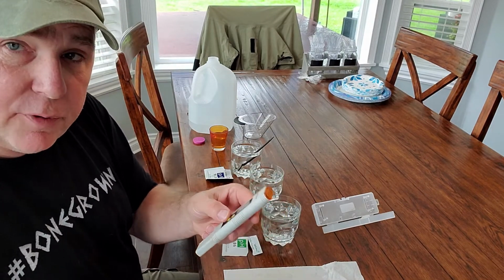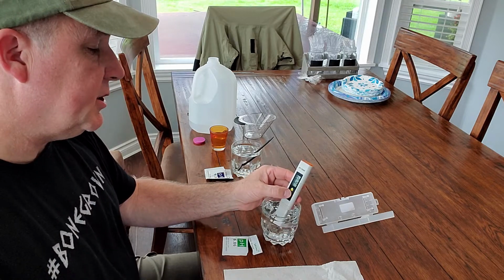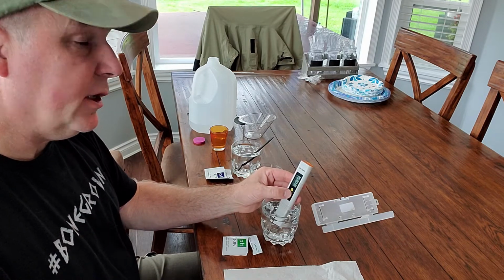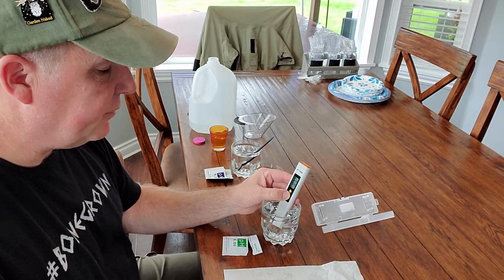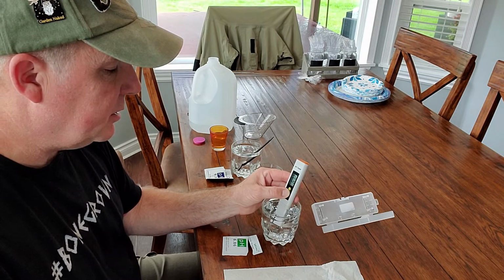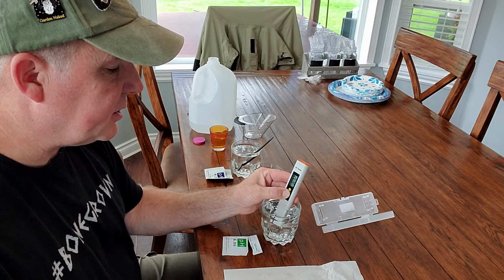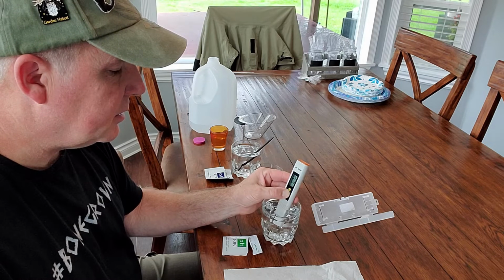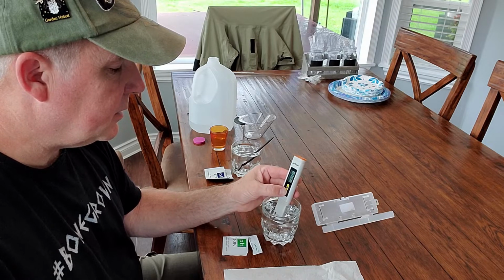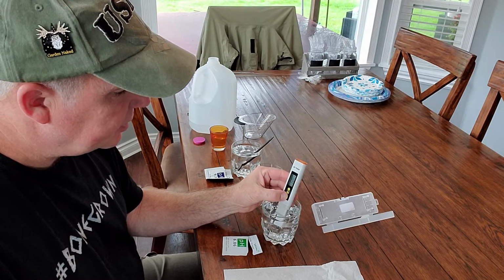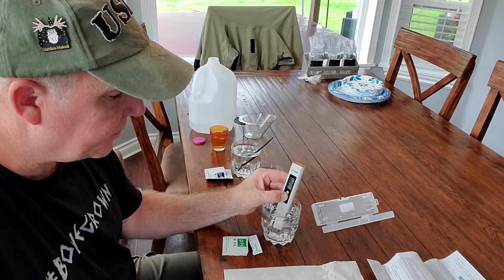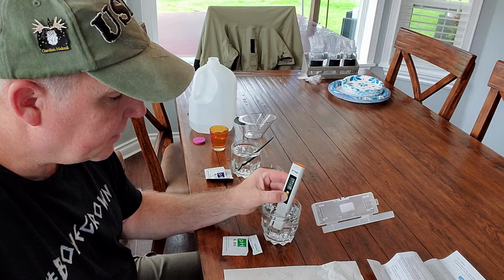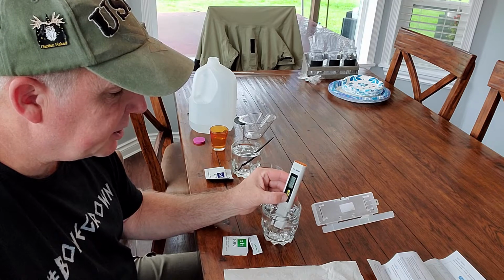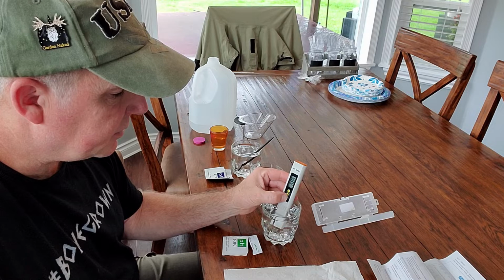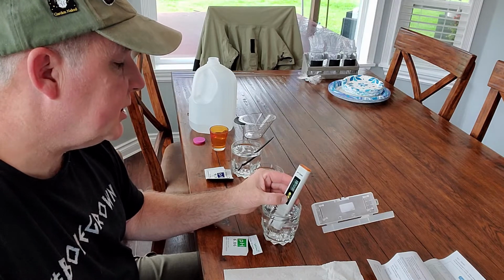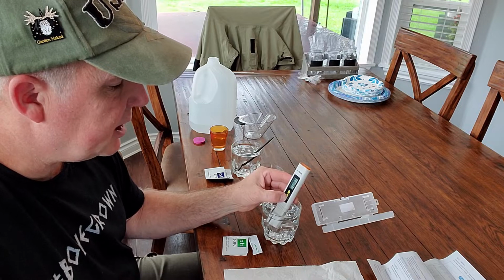So I know that I've got a problem, and I'm going to let it sit. You're always going to do the 6.86 on your first calibration. I'm going to hold it for 5 seconds. I'm going to put this in here. Now I release and it flashes, and it's at 6.87. So that's pretty good.